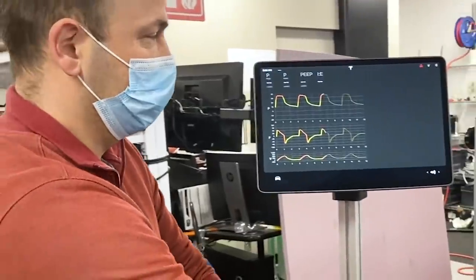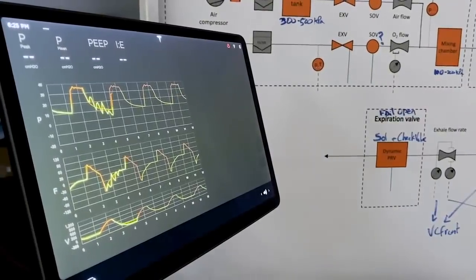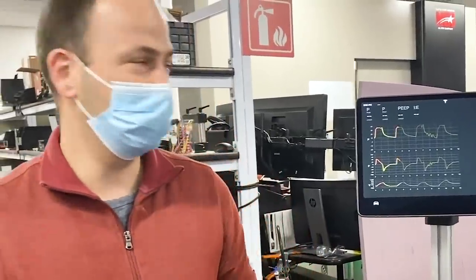Now if something happens to the lung and constricts it, you can see the pressure waveforms change overlaid on the history of the previous 12 seconds. That's important so the doctor can see if they're improving or something's going wrong.